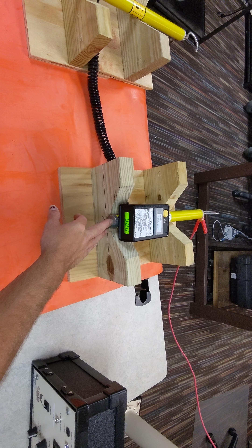It's not the ideal setup because of cramped spaces. If you're out in the field, then you may have a little bit more space. So we have a table here that we've lined with a rubber blanket that's been failed just to give a little bit added insulation from ground. We're using 2 sets of hot stick cleaning blocks in order to suspend the phasing meter.